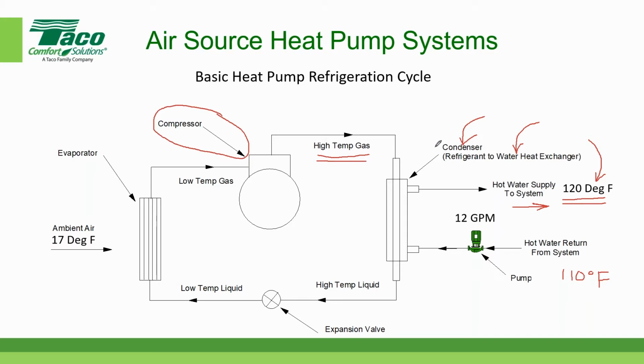That high temperature, high pressure gas enters the condenser, and then when we have our water coming into the refrigerant to water heat exchanger, it's going to cause that high temperature gas to condense and give up its heat to the water as it flows through the system here. So when the fluid leaves the condenser on the refrigerant side, it's now a high temperature, high pressure liquid. And it has condensed, as I said, and that allows us to heat the water from roughly 110 degrees through the heat exchanger, up to about 120 to 130 degrees. So I've shown 120 degrees today.